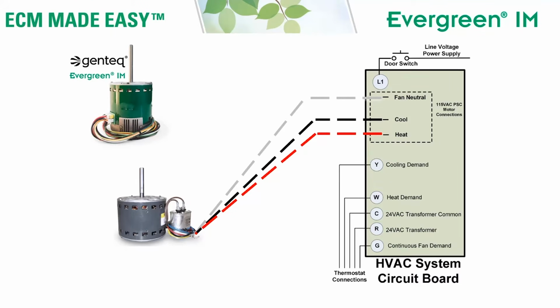Here we have a picture of a basic HVAC system circuit board. It has a heat tap and a cool tap. We have our PSC motor connected, 1 speed to the heat tap, 1 speed to the cool tap. And we have the 115 volt system, so we have the neutral wire connected to fan neutral. The first thing we're going to do is take the line voltage power connection, or high voltage power connection, from the Evergreen motor, and connect it directly to a continuous line voltage power source.